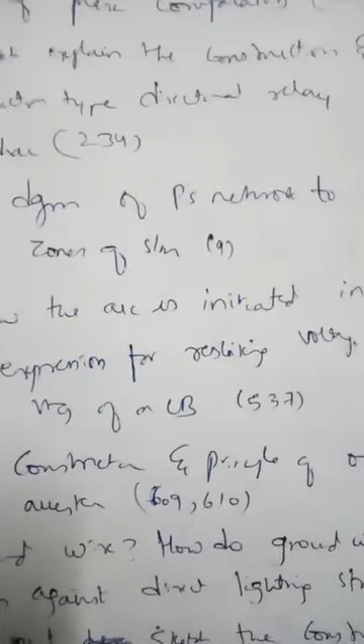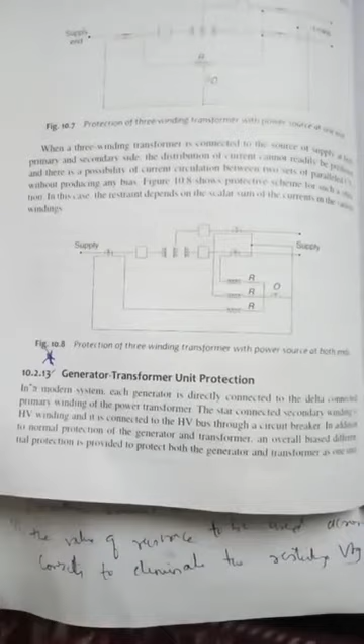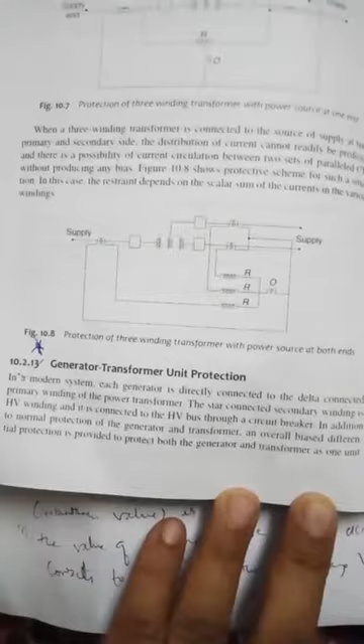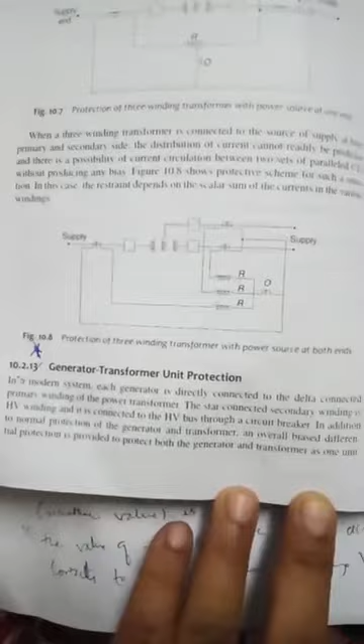Next we are going to see the long questions. First, the 11th one: explain generator transformer unit protection. So in a modern system, each generator is directly connected to the delta connected primary winding of the power transformer. Star connected secondary winding is the HV winding and it is connected to the HV bus through a circuit breaker. In addition to normal protection of generator and transformer, overall biased differential protection is provided to protect both generator and transformer as one unit. So we are protecting using a differential protection for transformer and generator as one unit, like this.